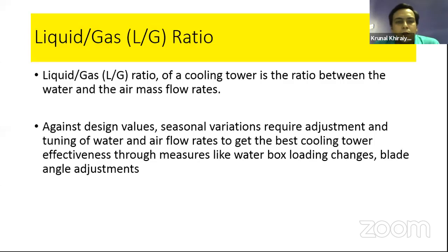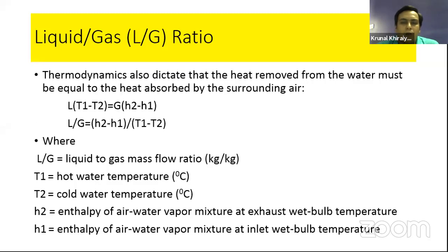Now we are moving towards the most important performance parameter, called the L2G ratio, meaning liquid to gas. So the liquid to gas ratio of a cooling tower is the ratio between the mass of water and the mass of air flow rates. Against the design value and the seasonal variations, we require adjustment and tuning of water and air flow rates to get the best cooling tower performance and effectiveness. So it is very important, and from season to season as well as in different operating conditions, we need to calculate the L2G ratio.